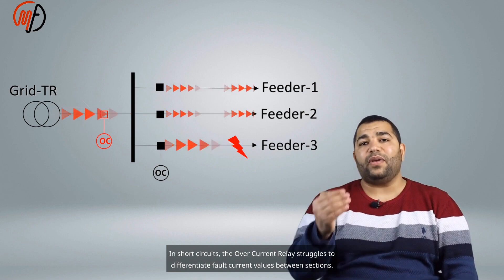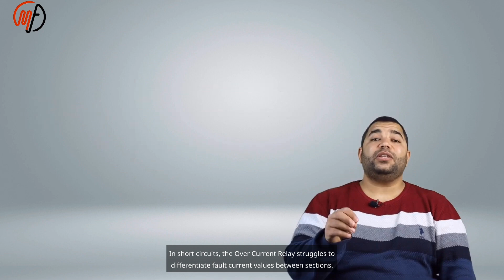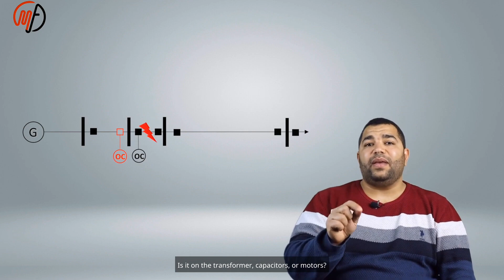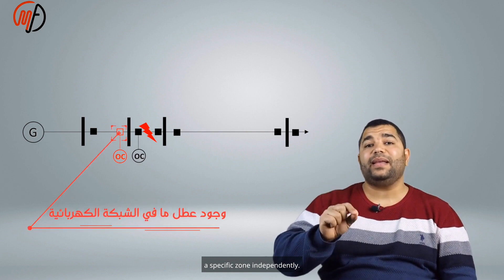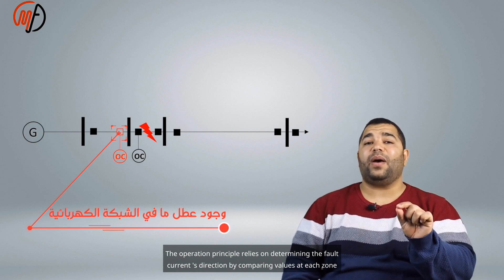These relays detect faults when current exceeds a set value. In short circuits, the overcurrent relay struggles to differentiate fault current values between sections. It indicates a fault but can't pinpoint the exact location. Is it on the transformer, capacitors, or motors? These challenges led to the search for a new protection method, resulting in unit protection, which protects a specific zone independently. This method compares electrical quantities. The operation principle relies on determining the fault current's direction by comparing values at each zone's start and end.